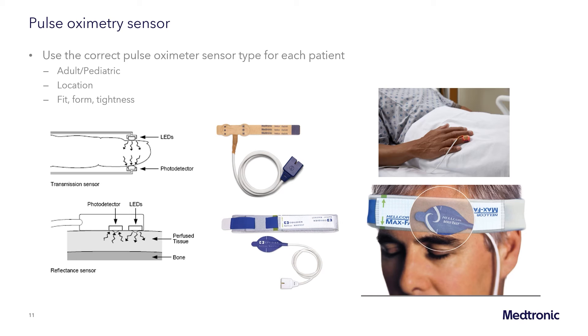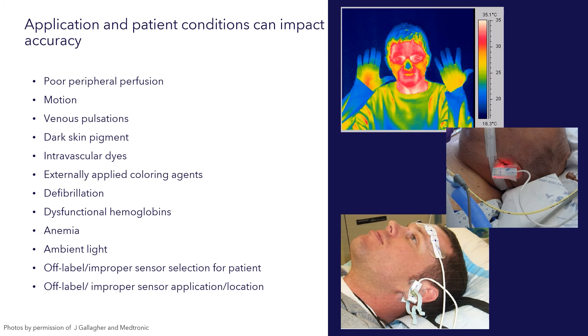There are a number of sensor application and patient conditions that can impact accuracy of the pulse oximeter. Two of the most common are poor peripheral perfusion as well as motion. While modern pulse oximeters have algorithms to mitigate these issues within reason, poor peripheral perfusion can result in a decrease in the pulse plethysmography waveform and the ability to properly detect oxygen saturation.